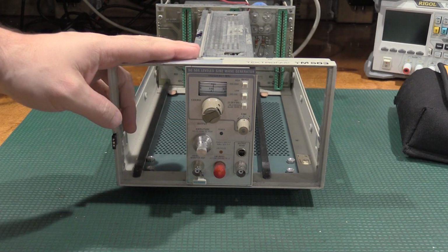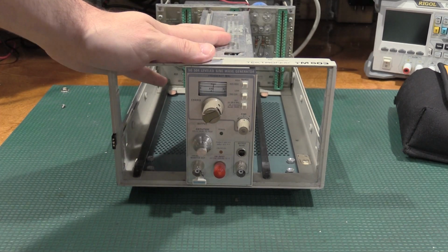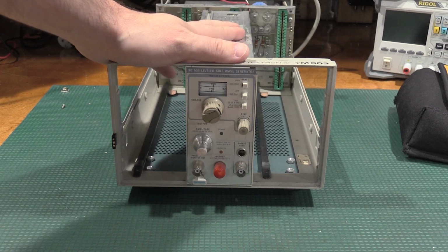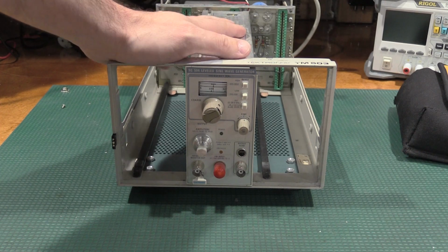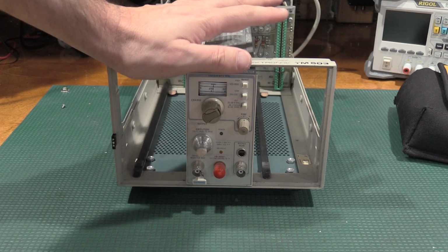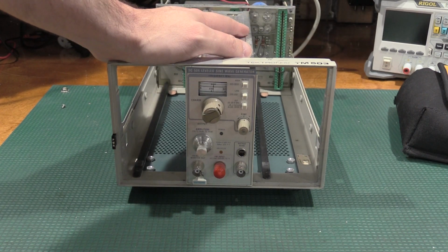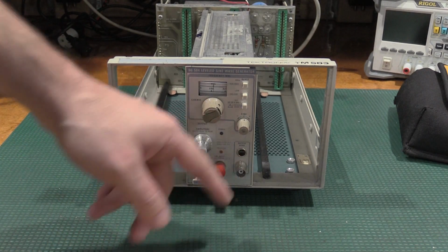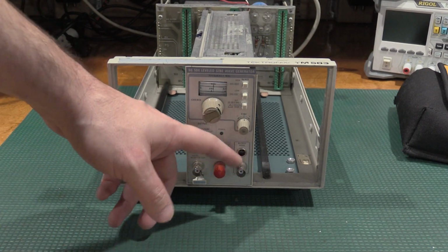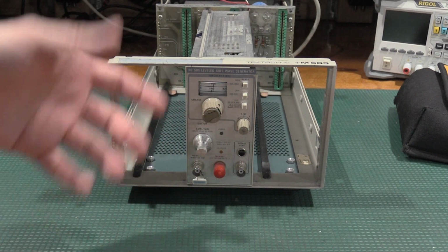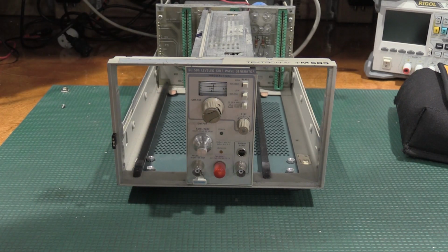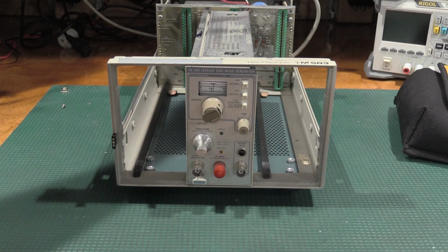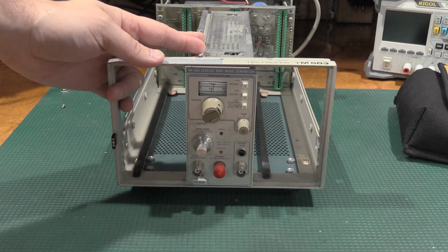One thing to note about these is if you're going to try to source one of these from the secondary market, almost every single one of these that I've seen does not have the leveling head. This unit will not work without the leveling head. Absolutely must have the leveling head. You can get RF out of the port, but it won't be leveled, so it won't be a leveled sine wave generator.